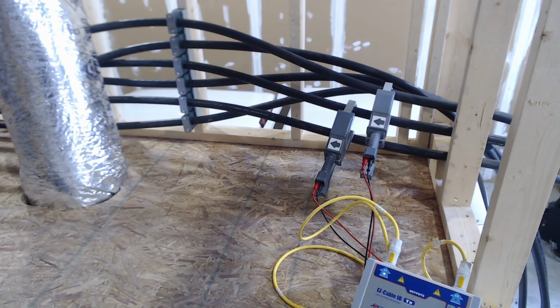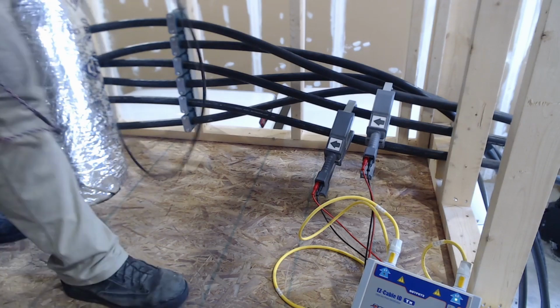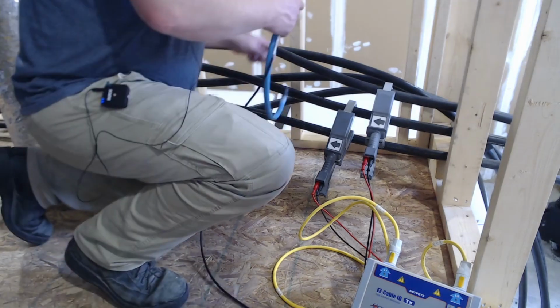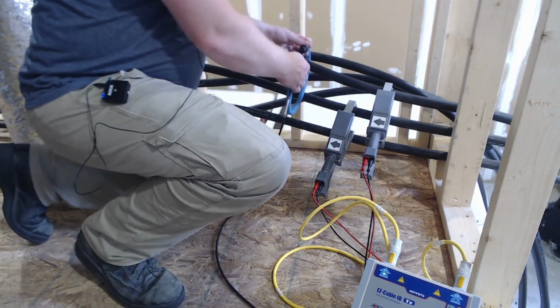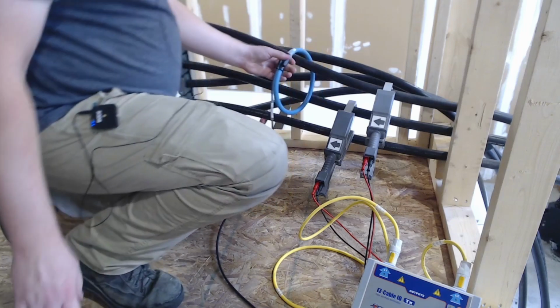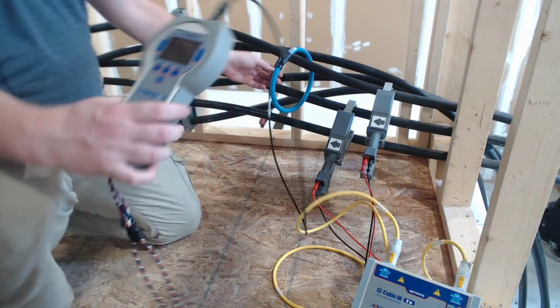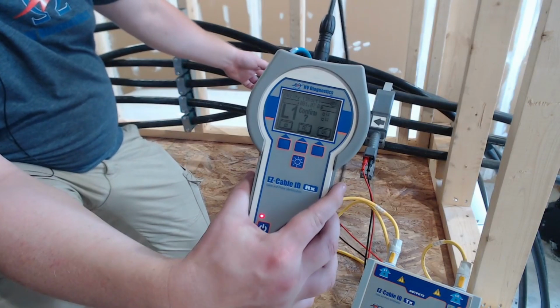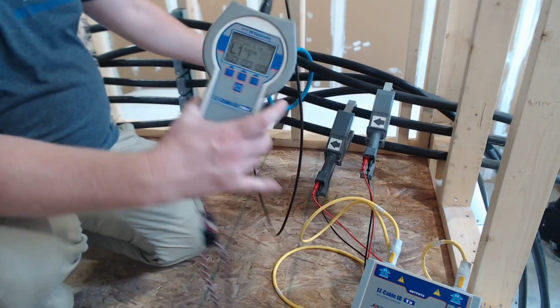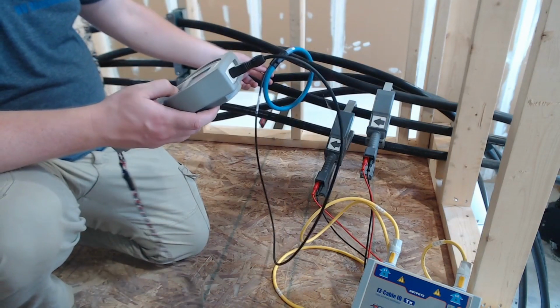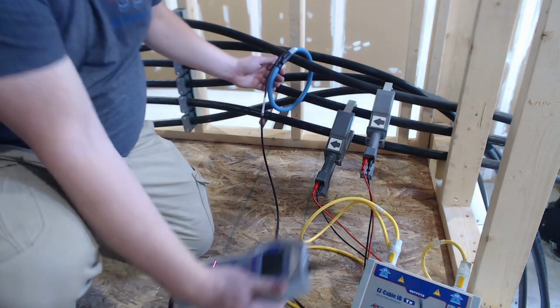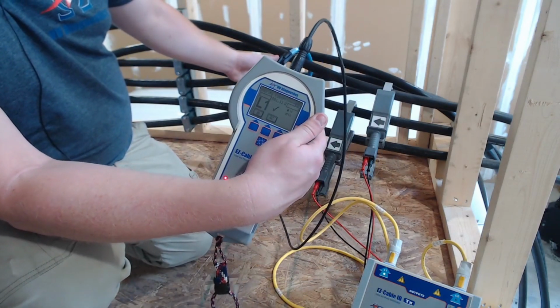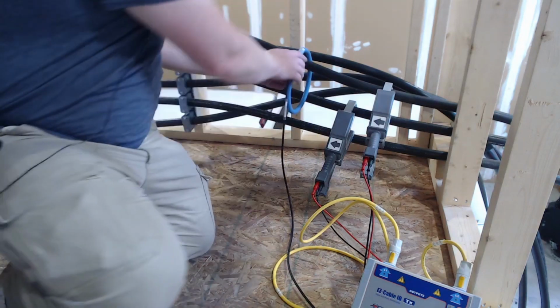So this is the calibrated mode. So we're going to go into ID, we're going to start a new session, and we're going to do short energized. So we're going to put our Rogowski coil over, and the way our setting is, we're set to face away from our transmitter. So now it's asking to confirm L1 because we're calibrating. We know we're on L1. Yes, we are. So now that we told it, it should give us a check mark. Yep. So we are check marked good.